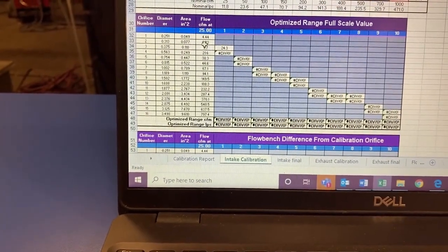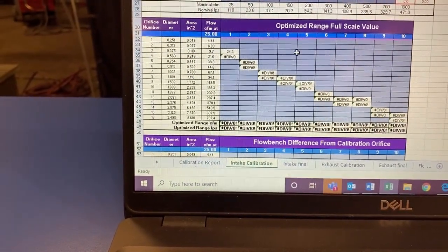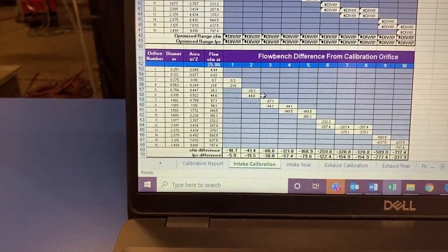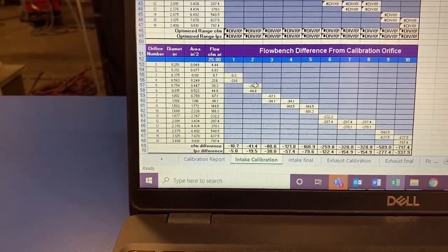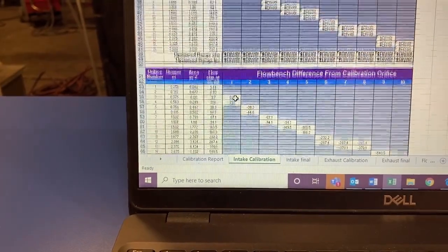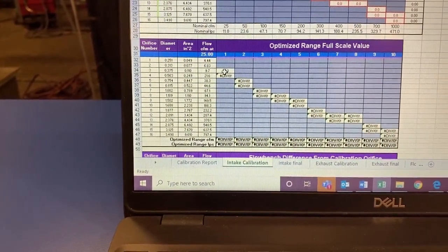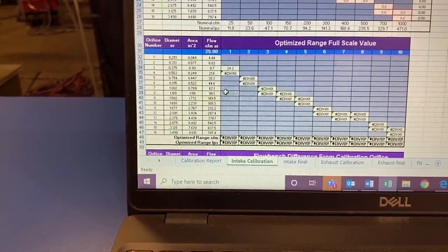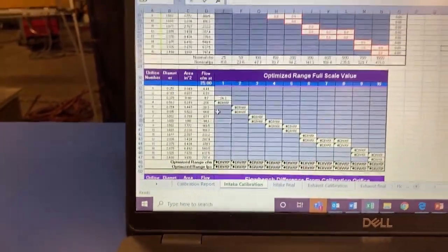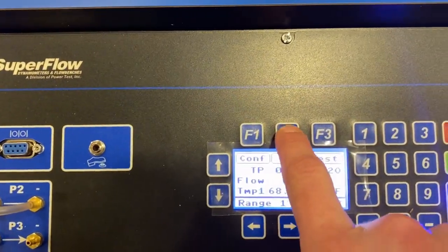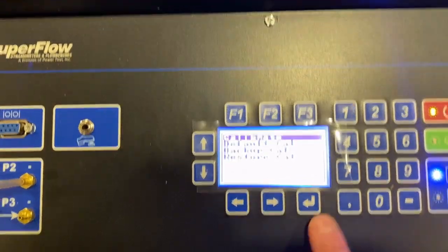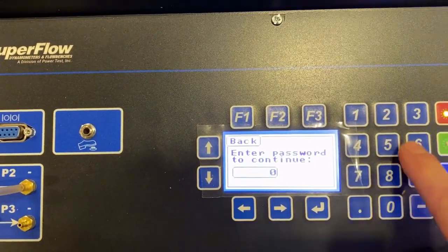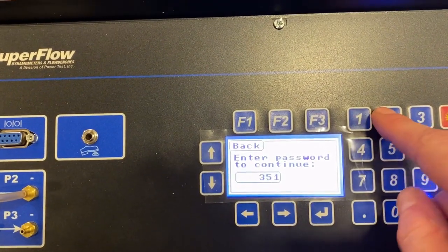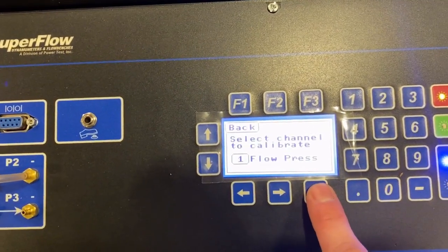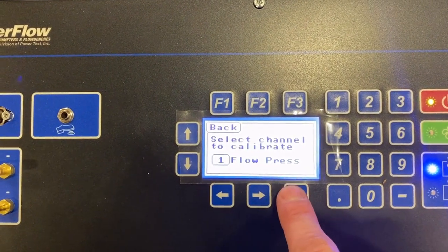You can see the corrected number shows up here on the chart below, optimized full scale value. This is the percentage difference. So you can see that it's 0.3% difference, or 0.3, sorry, CFM difference. This value here would then be used to adjust the bench, which we would be able to do by going into Calibrate, 3512 is the code. Select channel flow pressure.